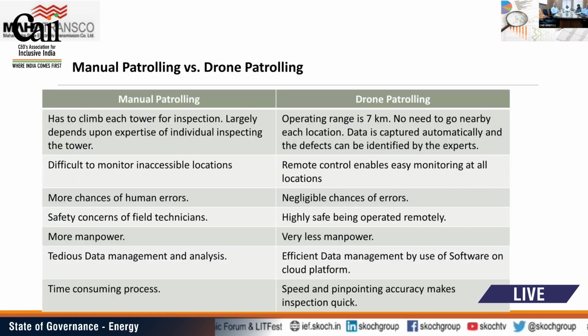To differentiate between manual and drone patrolling: in manual patrolling, one has to climb each tower for inspection, which largely depends on the expertise of the individual inspecting. It's a physical task. Some towers, as my colleagues from AP Transco can correlate, are up to 60-70 meters. It's a very tedious job to climb up and come back down, so there's always a physical limitation, and only one person can carry out the patrolling.